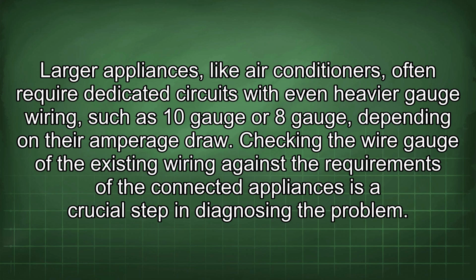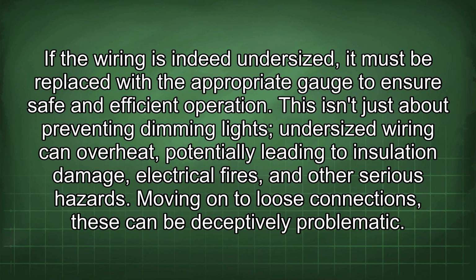Checking the wire gauge of the existing wiring against the requirements of the connected appliances is a crucial step in diagnosing the problem. If the wiring is indeed undersized, it must be replaced with the appropriate gauge to ensure safe and efficient operation. This isn't just about preventing dimming lights. Undersized wiring can overheat, potentially leading to insulation damage, electrical fires, and other serious hazards.